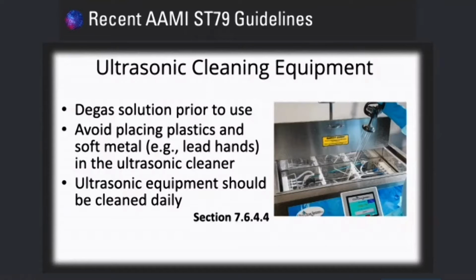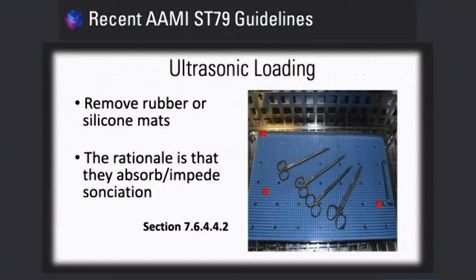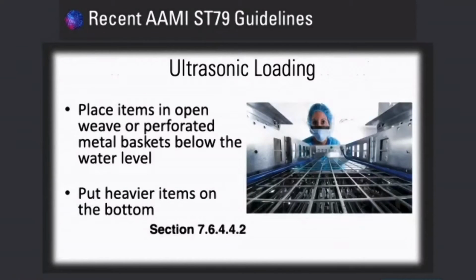Ultrasonic equipment should be cleaned daily. We'll talk a little bit more about that. Remove or don't use rubber or silicone mats. The rationale is that they absorb or impede sonication. It's kind of frowned on; using smaller trays to capture smaller instruments and things of that sort is recommended, but using rubber materials is not. For ultrasonic loading, place the items in open weave or perforated metal baskets below the water level and put your heavier items on the bottom.